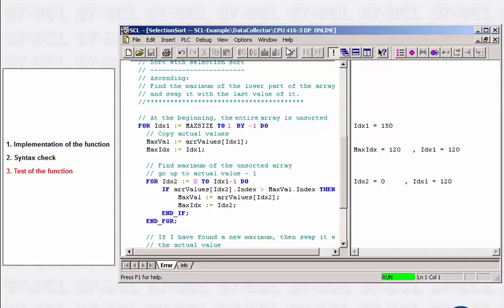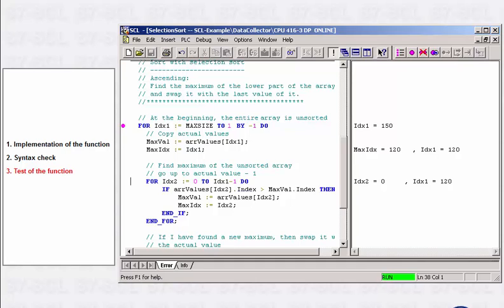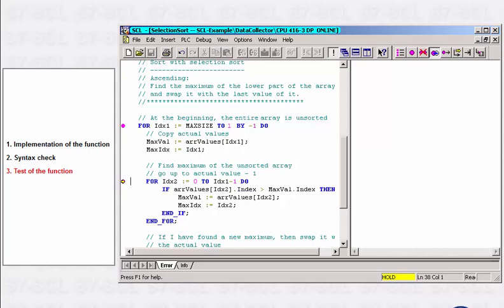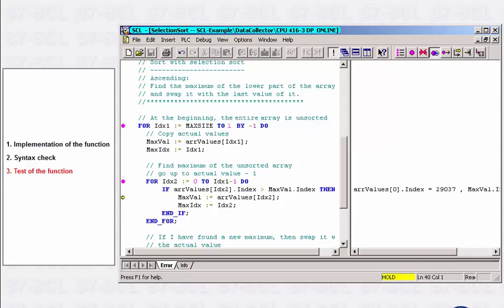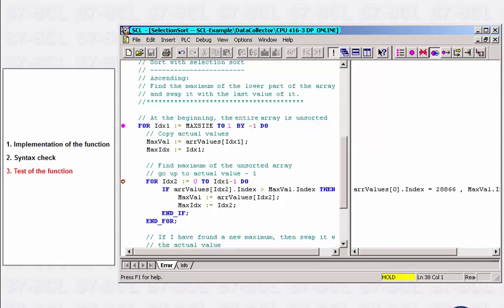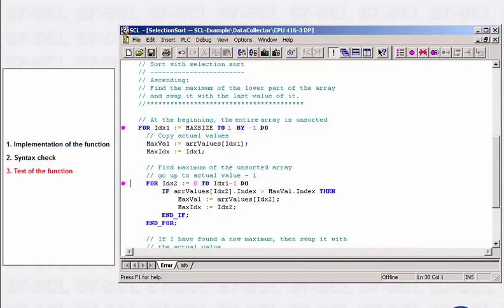In the case of highly dynamic processes, like the one we have here, it is best to use the single step mode with breakpoints. In just a couple of clicks, the controller will interrupt the cyclical operation at the breakpoints. By going through the code step by step, you can have the contents of each variable on the CPU displayed. The error search is simplified considerably in this way, making it possible to do simple module tests beforehand with S7 PLC SIM, for example. This reduces even more the risk of having to change the code on the plant and can thus shorten the commissioning phase enormously.